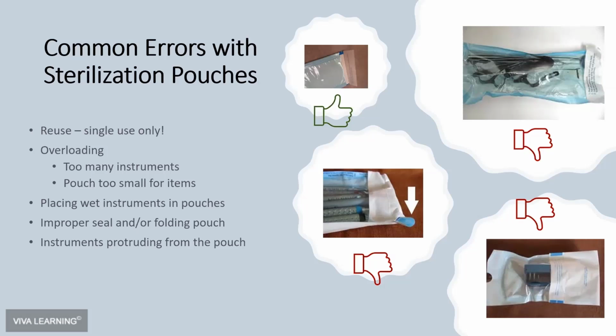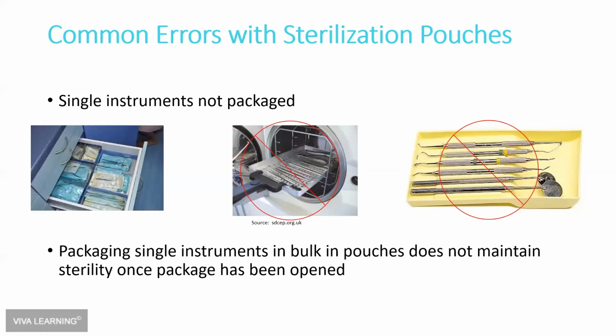So the proper way to seal a pouch is to score it, like the top left picture, fold it at the score, peel off the adhesive strip, and seal it so it's even, not so it's crooked, because you're going to get an improper seal. You could have some leakage from that pouch. So this is what I mentioned before about single instruments not being packaged to go in drawers.